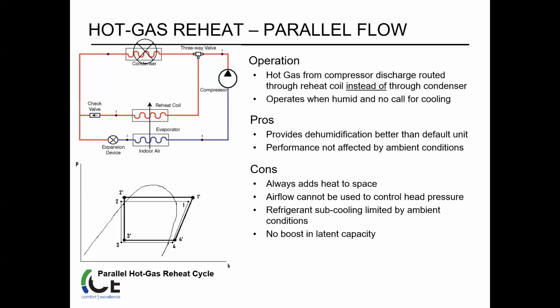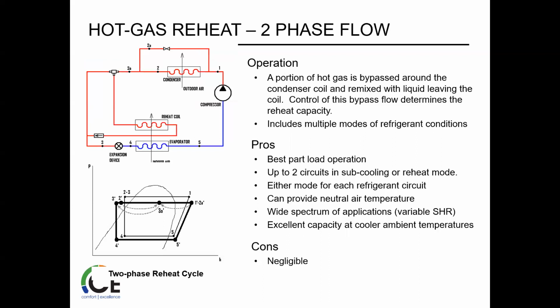So you've got series flow, parallel flow, and now a two-phase flow. Still very similar operation here. From the compressor, the hot gas refrigerant flows towards a condenser. In dehum mode, the condenser bypass valve controls the amount of hot gas bypass. So now we're starting to control it a little bit instead of just opening a valve and letting it do its thing. The amount of bypass determines the reheat capacity of the system. If more hot gas is bypassed, the reheat coil downstream will receive warmer refrigerant and heat the indoor air. So we're starting to change that a little bit.